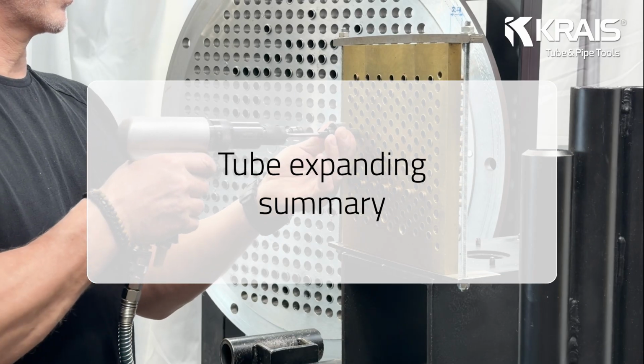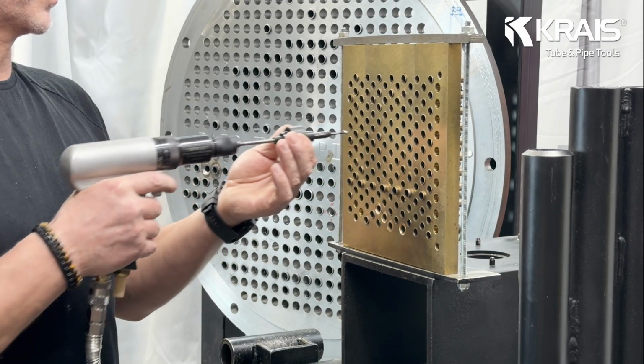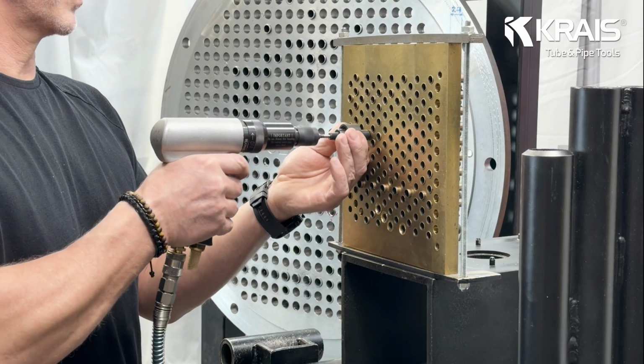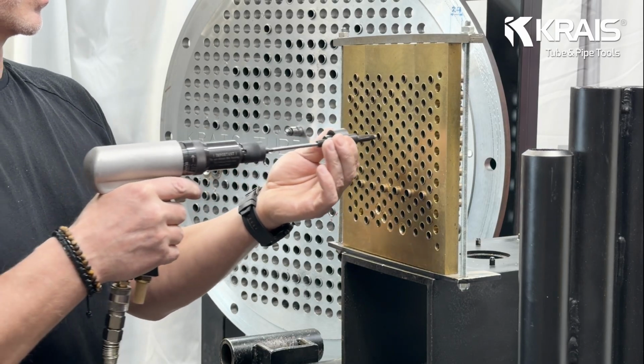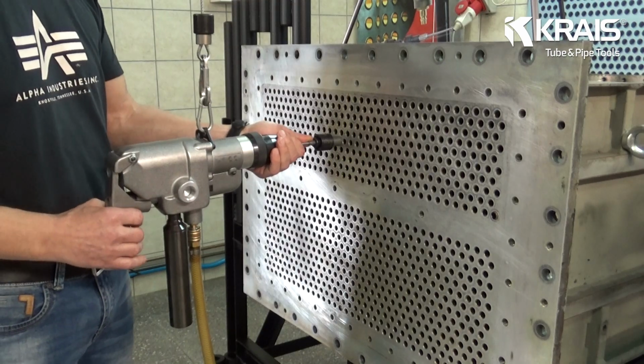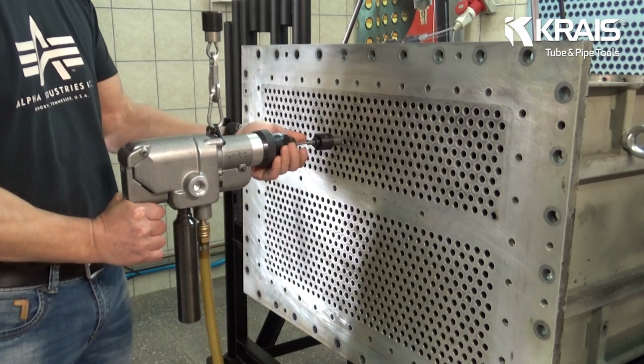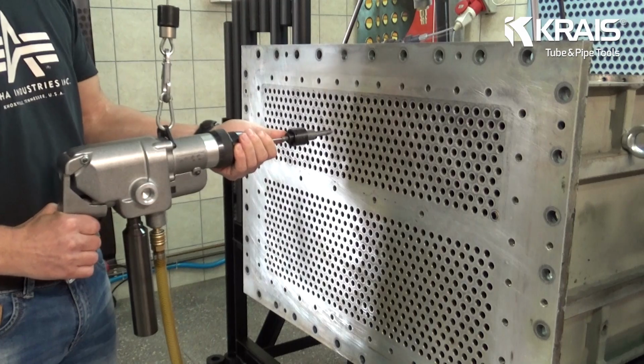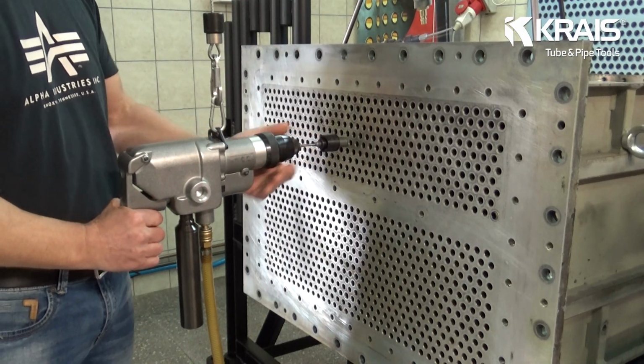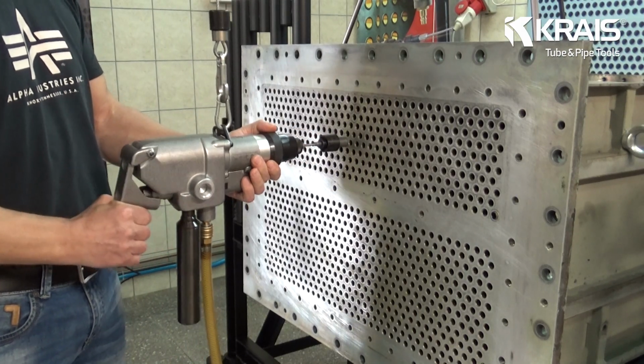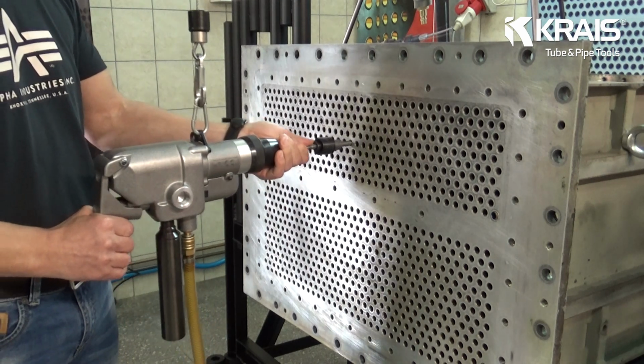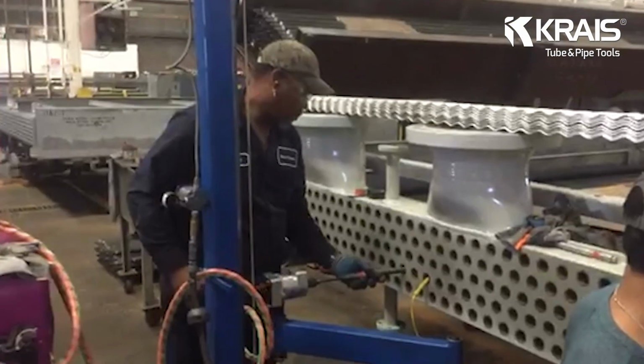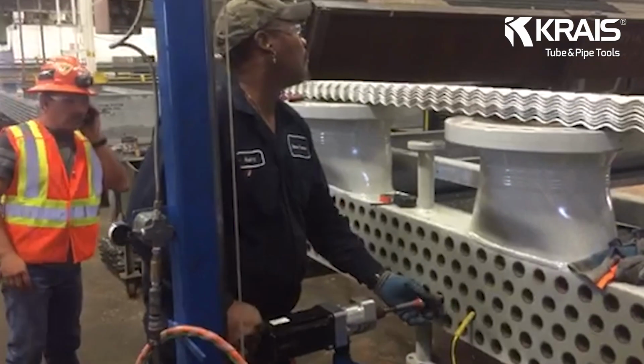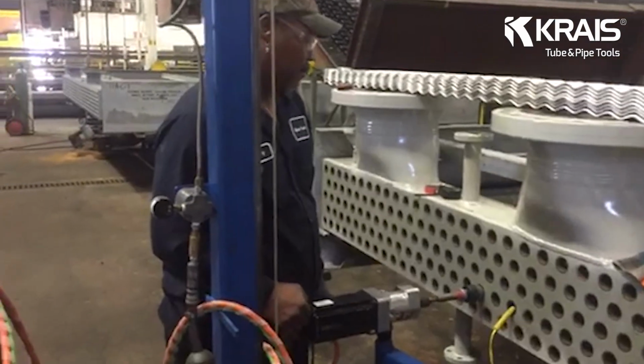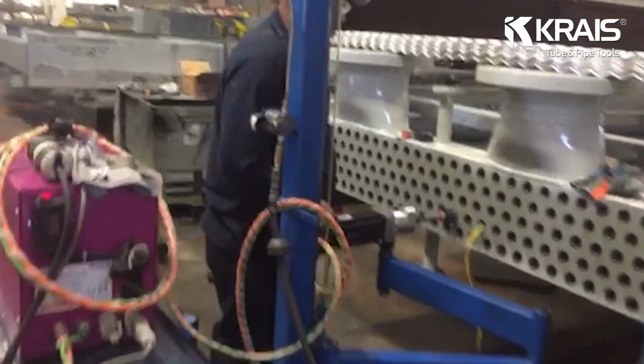If you take one principle from this video, let it be this: selection starts with tube OD and joint geometry, and it is finalized based on material, wall thickness, required control level, and reach, including whether the joint requires parallel expansion, controlled taper, flaring, pre-weld expansion, or beading. If you need selection support, send tube OD, wall thickness, material, tube sheet thickness, and the required joint type, and we will propose the correct configuration.